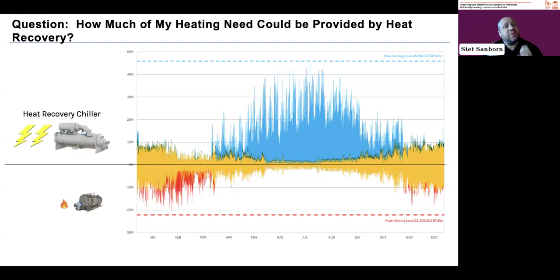Just swap out my chiller for a heat recovery chiller or a heat recovery heat pump. That keeps my connected load about the same, but uses my waste heat that I would dump off most of the year and puts it back into heating the building. This works especially well if you have a hydronic-based building. It saves a ton of money operationally and gives a lot of carbon savings. And the boiler is still there for backup. If you ever have to replace that boiler, it's likely it can be quite a bit smaller.